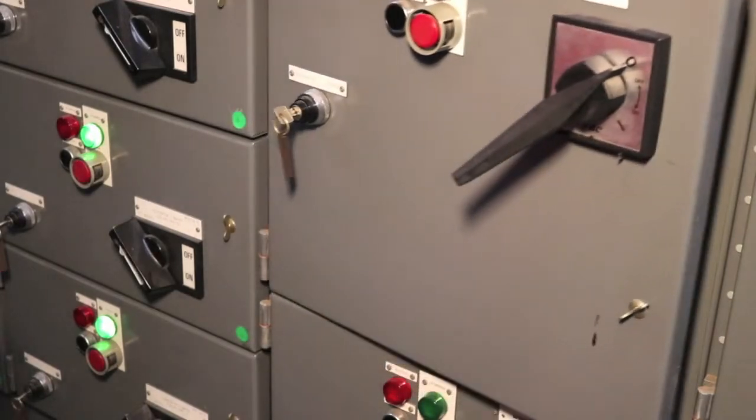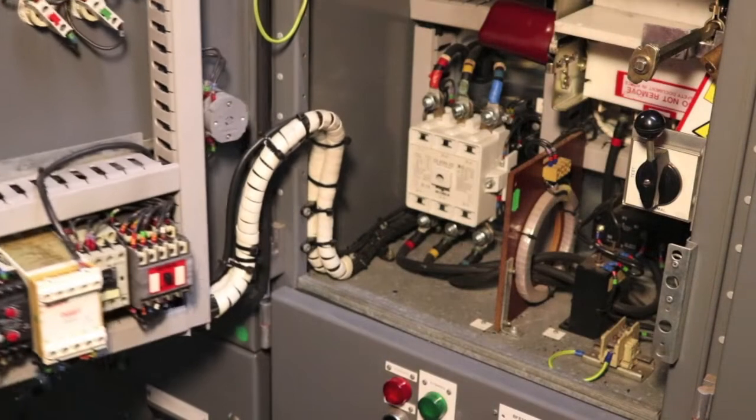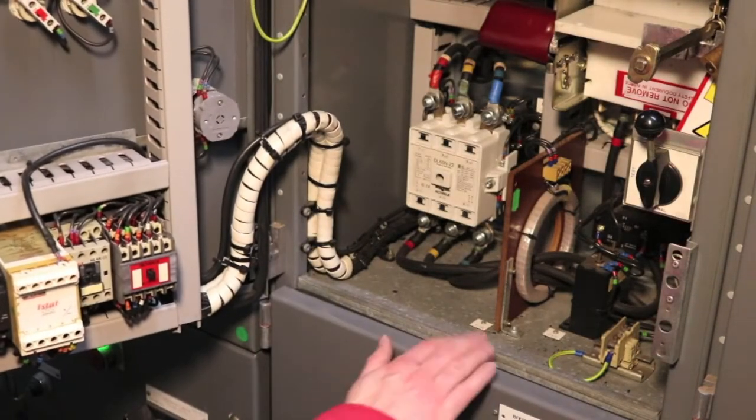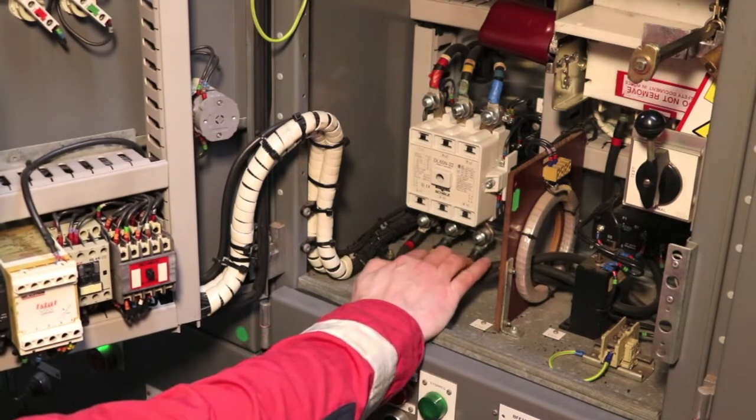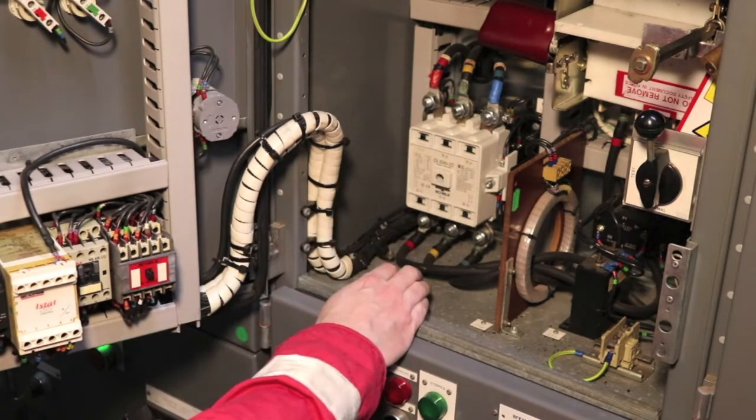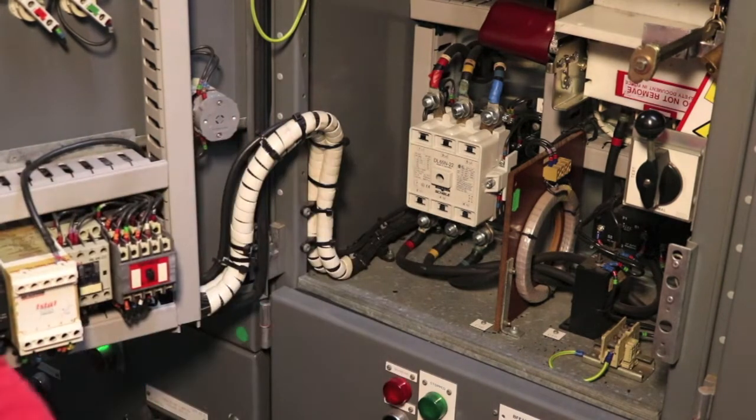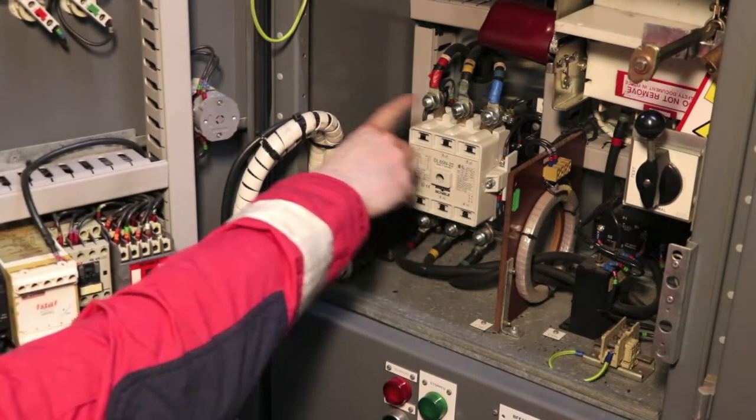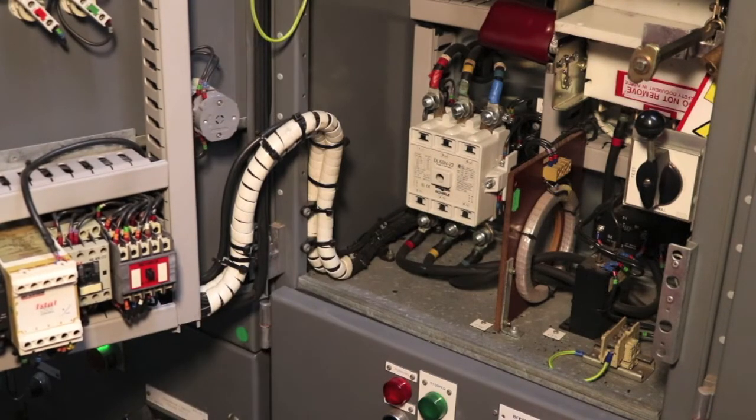This is the 45 kilowatt motor starter cubicle and inside we've got the mains that comes in on the right hand side to the bottom of the contactor and the motor terminal is going out at the top. All the electrical tests have been done at these terminals at the top of the contactor going out to the motor.